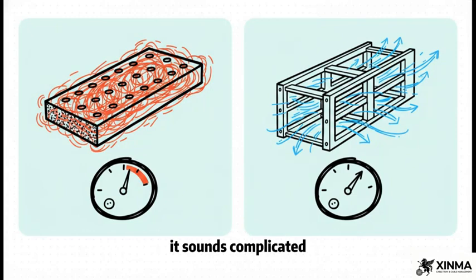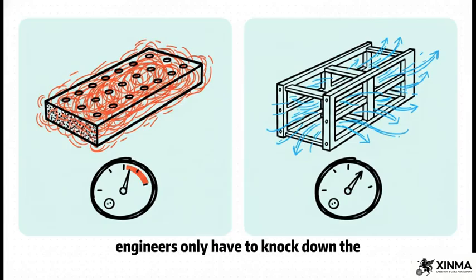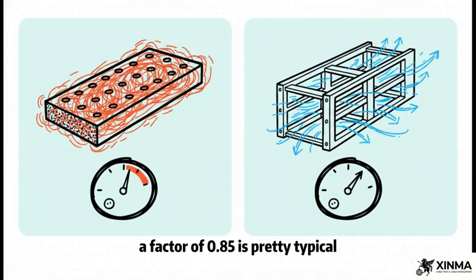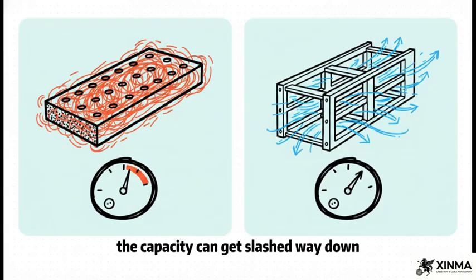It sounds complicated, but it's not. Since the ladder tray is so good at getting rid of heat, engineers only have to knock down the cable's max capacity by a little bit. A factor of 0.85 is pretty typical. But with a perforated tray, all that trapped heat forces them to be way more cautious. The capacity can get slashed way down, sometimes to a factor of just 0.60.